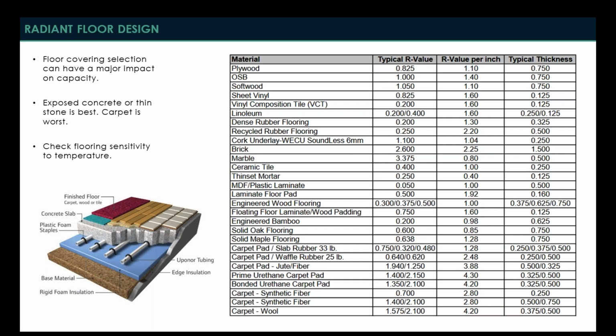Now, the reduction in capacity varies depending on what it is that you're looking at. So if you're looking at maybe a thin, dense stone, it's not going to have that much of an impact on capacity. But when you start to look into wood flooring and you start to look into even carpet, now you're really reducing the capacity of the system, and you need to evaluate whether a radiant floor is going to be the right application.